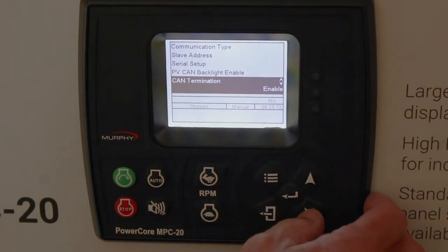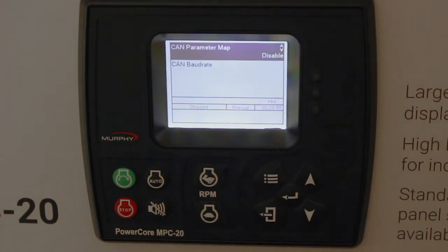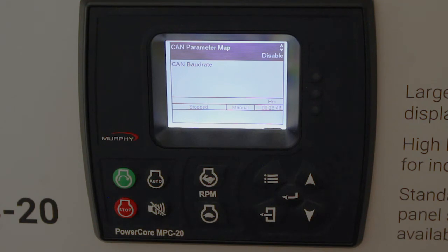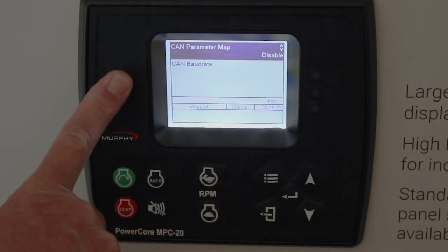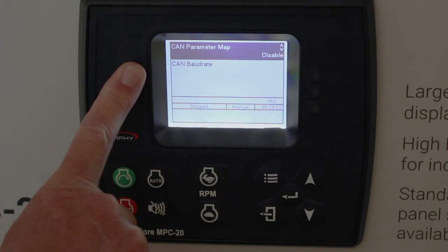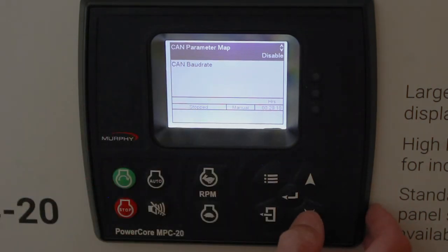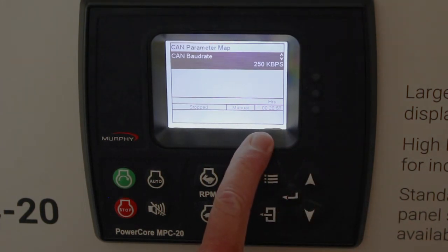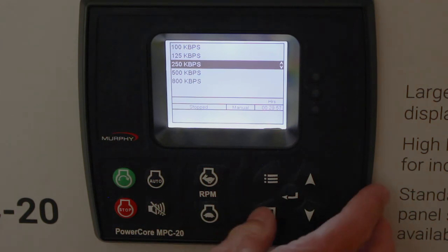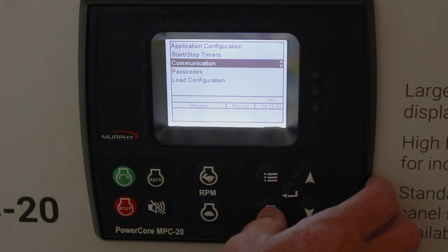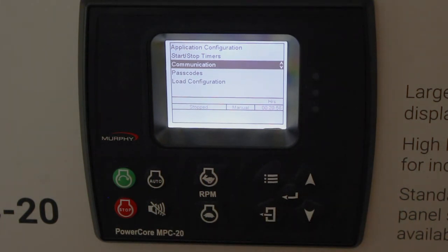The CAN parameter map is similar to the Modbus map — same idea, but accessed through the CAN port. If telematics folks don't have RS-485 and only have a CAN port, they can hook up to the CAN port and query our CAN parameter map to get the same type of control and display items. It's disabled by default. If they're using the CAN parameter map, they could still drive PVA gauges off the RS-485 port. The CAN baud rate is 250 kbps — you can adjust that. Hitting the back button gets us back to the main menu, and that concludes the Communication Menu video. Thank you.